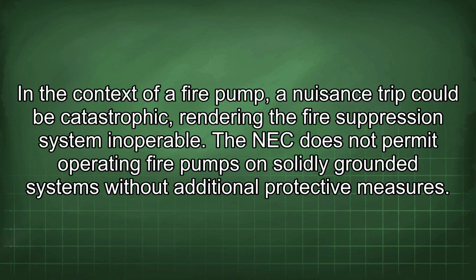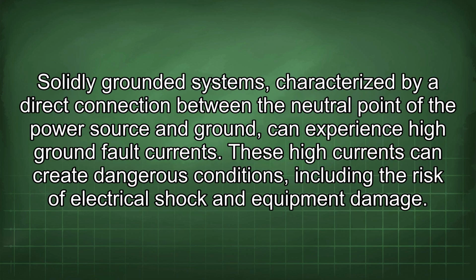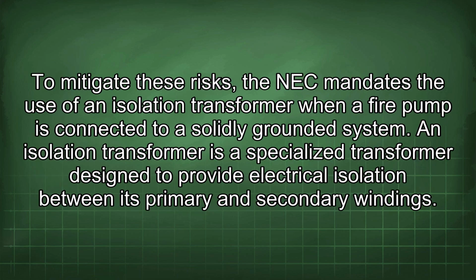The NEC does not permit operating fire pumps on solidly grounded systems without additional protective measures. Solidly grounded systems, characterized by a direct connection between the neutral point of the power source and ground, can experience high ground fault currents. These high currents can create dangerous conditions, including the risk of electrical shock and equipment damage.